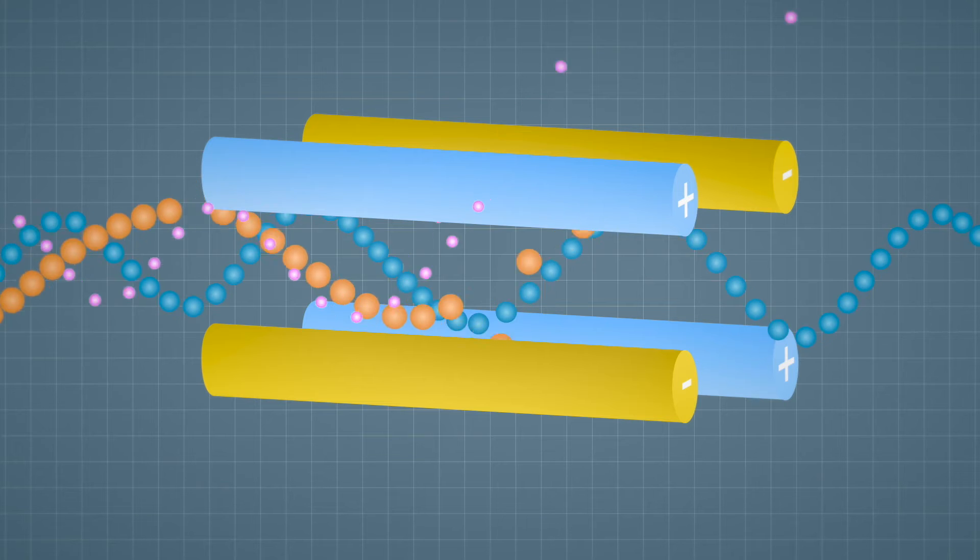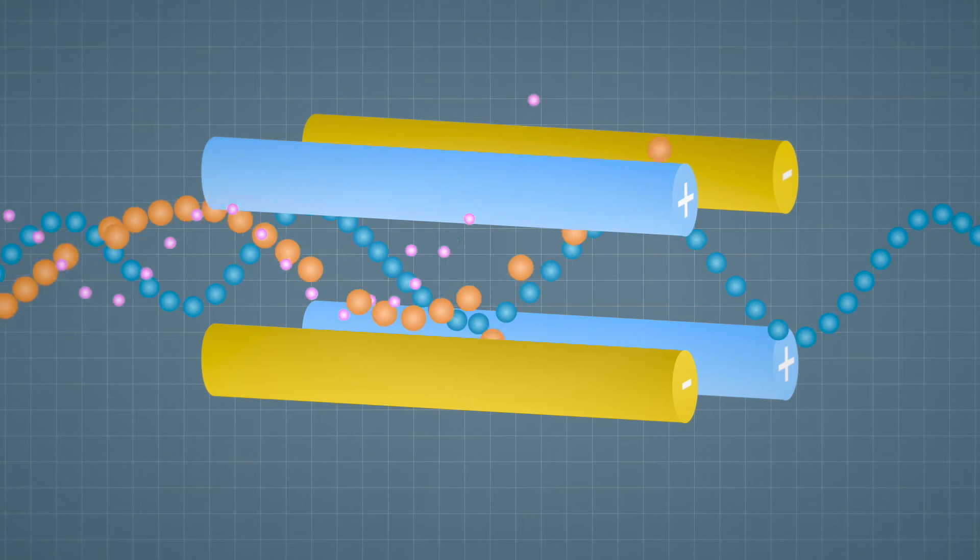The ion motion within a quadrupole is relatively complex, so we won't go into details here. It's possible to plot ratios of the RF and DC voltages for which the ion motion does not extend beyond the inscribed radius of the rods in the X and Y axis. In other words, we can derive ratios where the ion motion is stable.